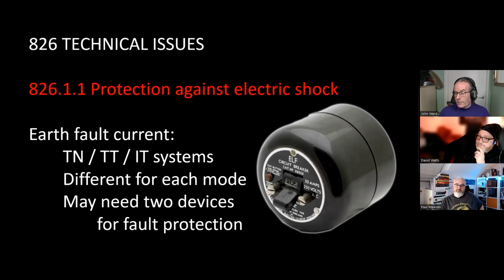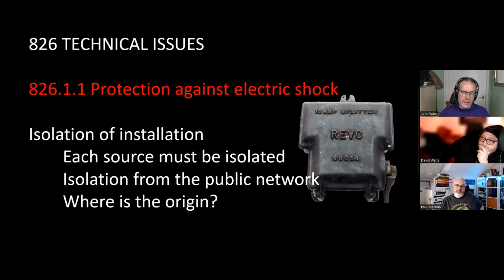And earth fault current, as you hopefully should already know, is going to be completely different in TN, TT, and IT systems, IT being isolated, not to do with computers. It's going to be different for each mode, and you may need 2 or more devices for fault protection. So if you were connected to the grid as a TN system, and then you change over to TT, again, the fault current there is going to be completely different. You may need to put additional things in. And most importantly, each source must be isolated, and that's talking about the grid, your battery storage, your solar, wind generation, all of this other stuff.